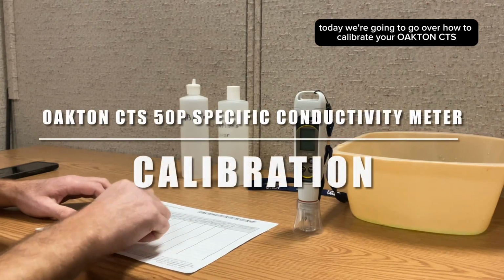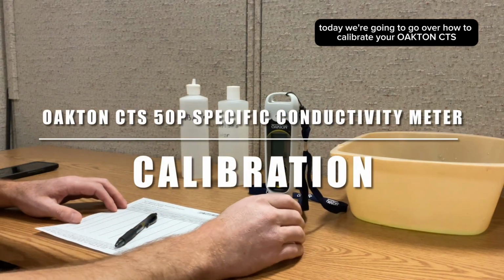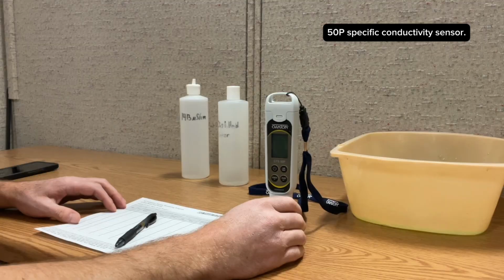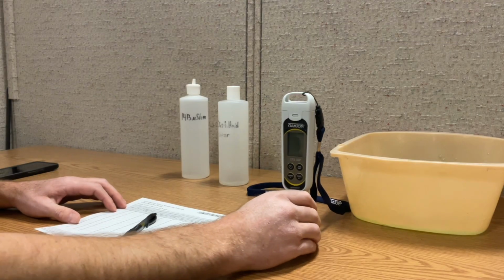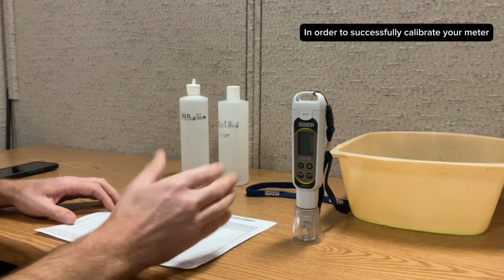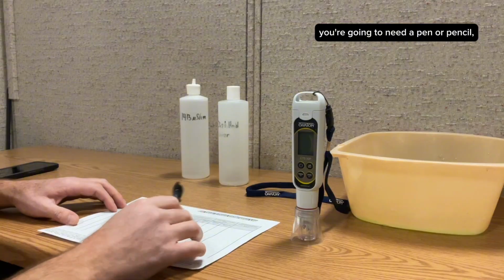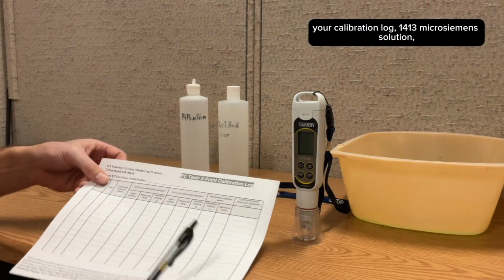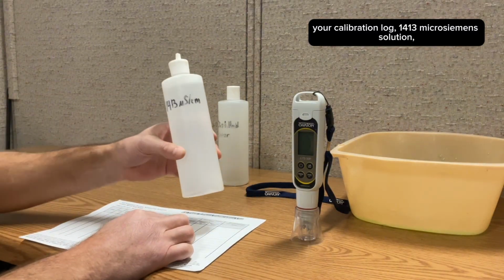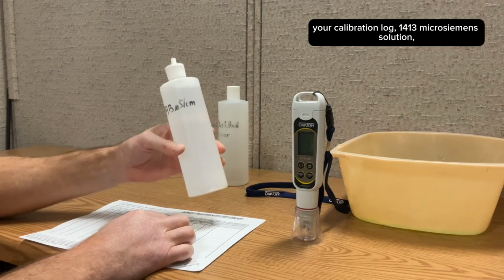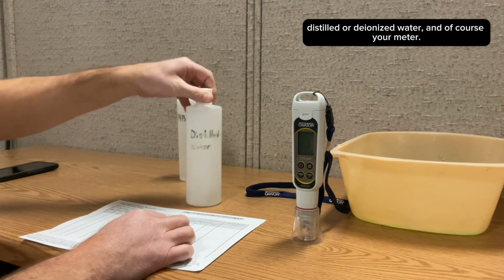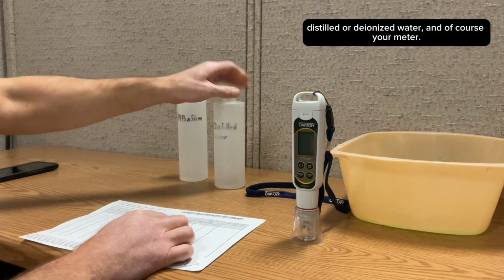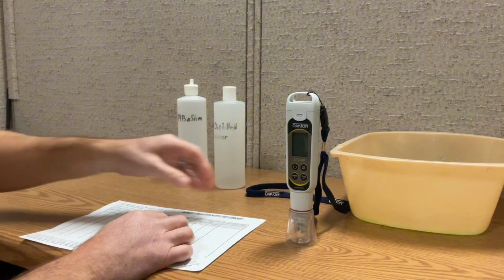Hello, today we're going to go over how to calibrate your OAKTON CTS 50P specific conductivity sensor. In order to successfully calibrate your meter, you're going to need a pen or a pencil, your calibration log, 1413 microsiemens solution, distilled or deionized water, and of course your meter.